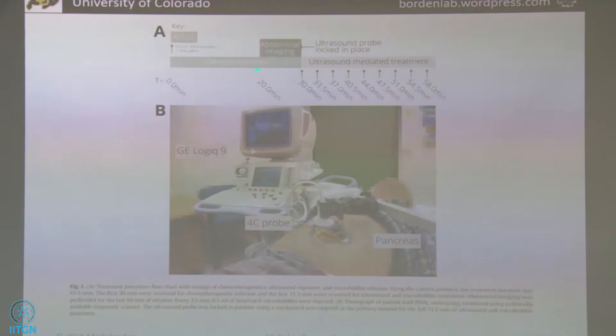And they're also doing some imaging just to make sure that the probe is over the region that they want to do. And they're not even sonicating the entire three-dimensional volume of the tumor. They're just giving a slice. We were talking about this, the problem with imaging is you're just getting a slice, you're not getting a three-dimensional view. So there are approaches that are being implemented now and are under research and development to do 3D, but right now it's 2D. Okay? So there's a 2D slice through the tumor. They find the largest cross-section of the tumor, and that's what they use.